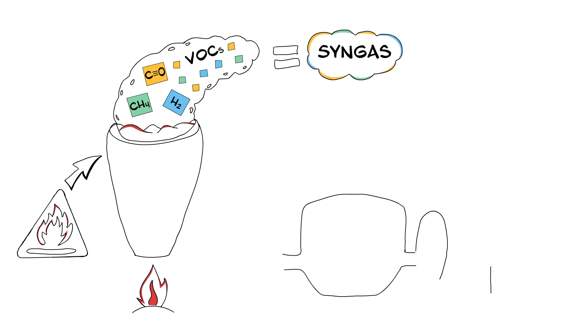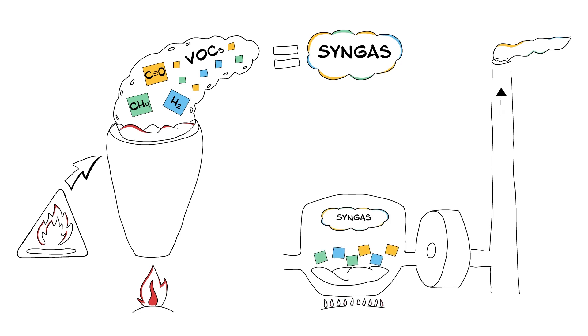Syngas is usually discharged to the atmosphere without significant hazard. However, it can accumulate within combustion or drying systems, including ducts and cyclones, if the process ventilation system does not extract the syngas effectively. For example, during a power failure or outage, the combustion or drying system can continue to create syngas with a restriction or complete loss of ventilation within the system.